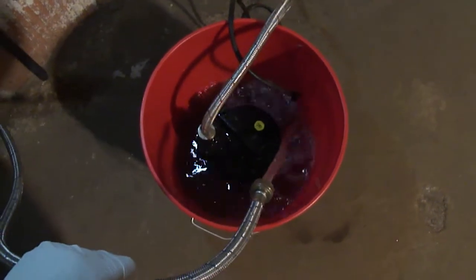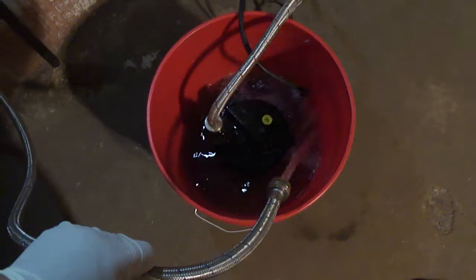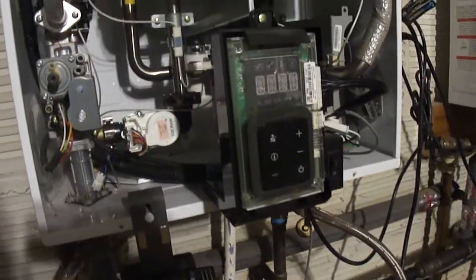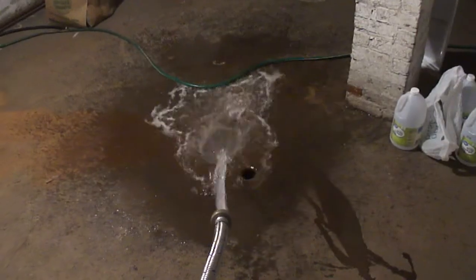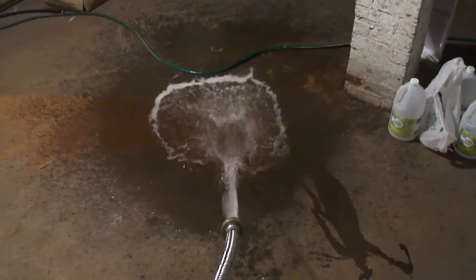In this particular case, our machine is dip switch number 6. Once you set that, it'll open up the solenoid and allow you to purge the whole heat exchanger with vinegar. If you have done this right, you'll see that the pump is pumping right through the heat exchanger, and your machine should be off. Rinse the unit with clean water afterwards.